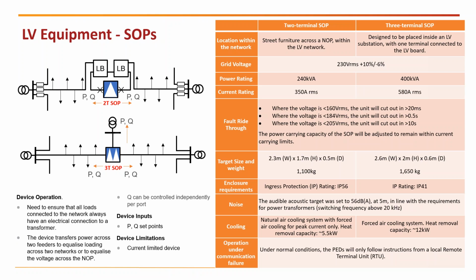So what are these devices? For the soft open points, we will deliver 2 different types of power converters. One is called 2-terminal and one is called 3-terminal. The 2-terminal SOP is called that, as you can see from the presentation, because it's connecting 2 secondary substations. The 3-terminal is connecting 3 secondary substations. The basic function is to enable power sharing, the mutual support between 2 or 3 secondary substations when required, in order to release capacity on our LV network, particularly at different times of the day when the load is at a different level on different parts of our network.